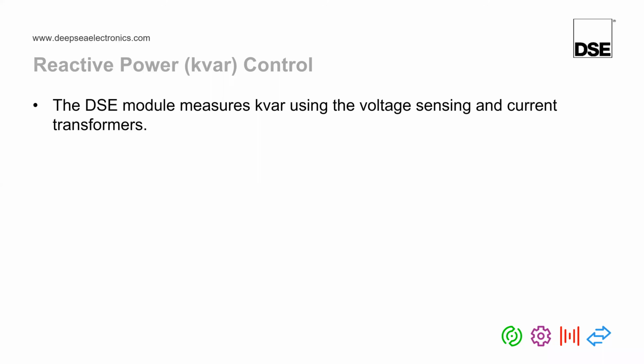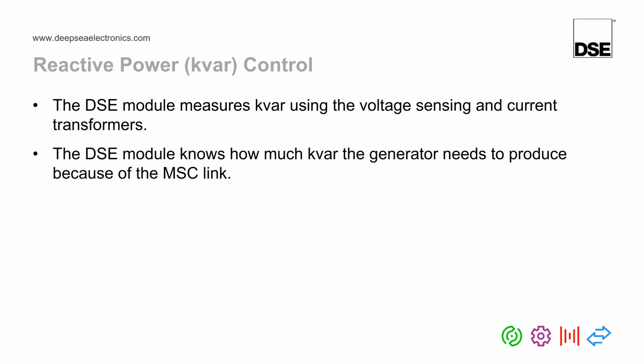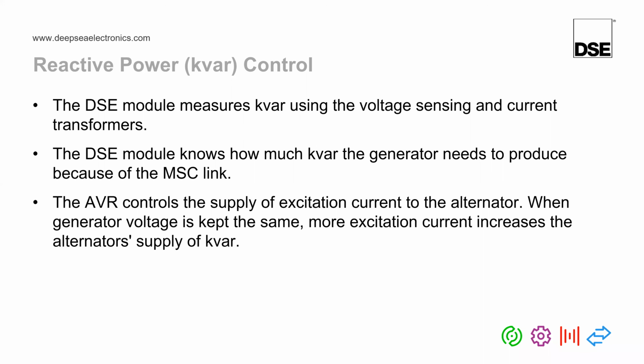The same can be said for the other type of power that the DeepSea module needs to share. This is called reactive power, mostly known as kVARs. The way the DeepSea module measures kVARs is by using voltage sensing and current transformers, just like with kilowatts. It knows how much kVAR the generator needs to produce because of the MSC link, again, just like with kilowatts. The only difference here is the way the DeepSea module controls kVAR is by varying the control to the AVR. If the AVR varies excitation current, it will actually vary the amount of kVARs the generator produces. So it's very important that the DeepSea module has good control.